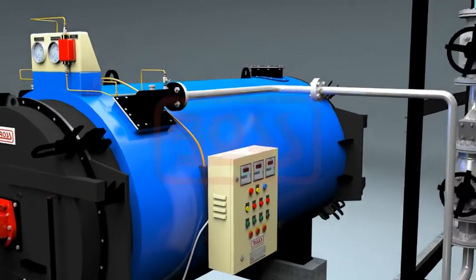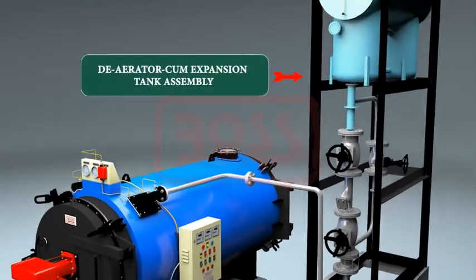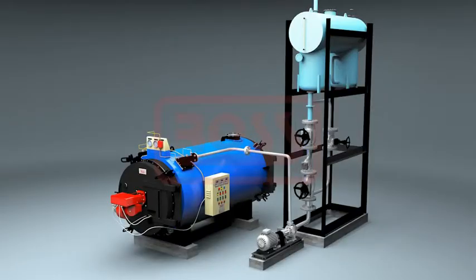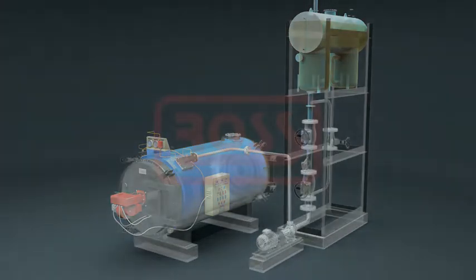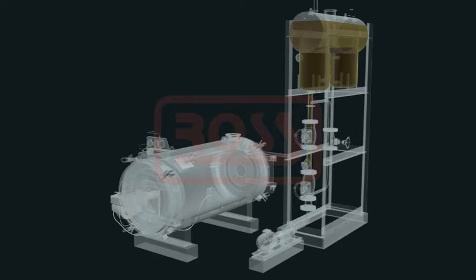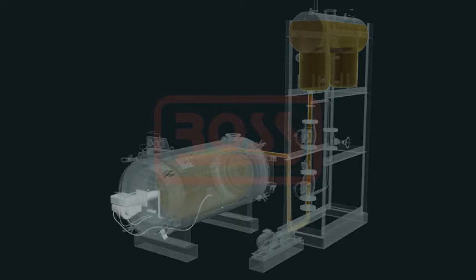The de-aerator cum expansion tank assembly. Typical working cycle: Thermal oil is filled in the closed-loop system. The de-aerator tank is placed at highest elevation in the heating circuit. Thermal oil pump is run continuously. Fuel firing switch is put on to run the burner.